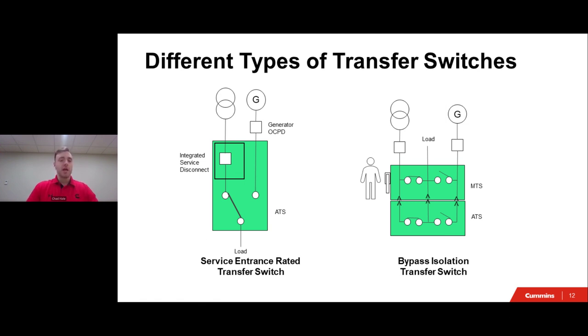So lastly, we have this bypass isolation transfer switch. A simple way of viewing a bypass isolation transfer switch is that you have two switches sandwiched together. And in this diagram, you have an automatic transfer switch on the bottom and a manual transfer switch also integrated into the switch itself. In normal circumstances, both will be connected, but for this instance, let's just say that there is a need to do some maintenance on the automatic transfer switch, or there is some other need to take the automatic transfer switch out of commission.